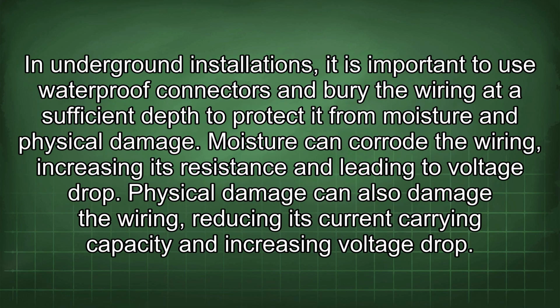In underground installations, it is important to use waterproof connectors and bury the wiring at a sufficient depth to protect it from moisture and physical damage. Moisture can corrode the wiring, increasing its resistance and leading to voltage drop. Physical damage can also damage the wiring, reducing its current carrying capacity and increasing voltage drop.